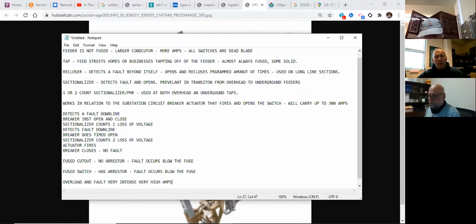Okay? When this occurs, either the overload or the fault, the switch is going to open. You can take the fuse out of the fuse barrel. We've done this out in the field where we replace the fuse. And a melted fuse, what we call a melted fuse, is an overload. You take the fuse out of the tube, and you can still see the connections of the fuse inside that have melted away. All right?